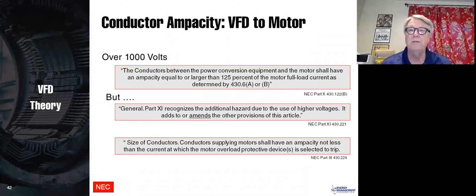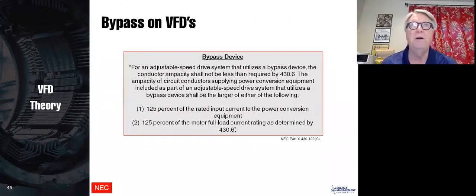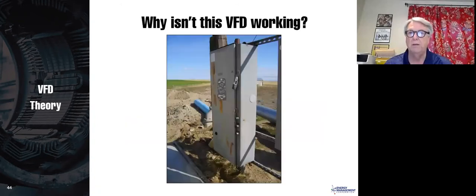Now, if you go over 1,000 volts, that changes a little bit, and I'm not going to go through how this all happened. The NEC 2020 made it more confusing than the NEC 2017, but the fact is that the input to a drive over 1,000 volts needs to be 125% of the input amps to the drive. The output, however, the cable can just be sized to wherever the VFD is programmed to trip. So there is a difference there between medium voltage and low voltage VFDs. If you have a bypass device, then of course you have the ability to run the motor across the line, and then that 125% is the same, but still based on the National Electrical Code.